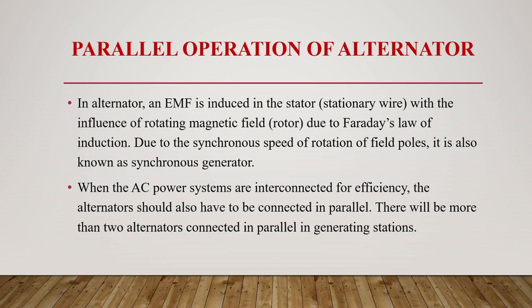The demand for electrical energy will always be there, and it will grow at a steady pace. Electrical utilities and others find it necessary to increase the generating capacity at regular intervals. So it is not economical to discard the serviceable alternator or alternators in favor of larger ones. So it will become necessary either to operate alternators in parallel or to subdivide the load and feed it from multiple isolated systems. Out of these two, parallel operation is more preferred than operating many single units at different times.